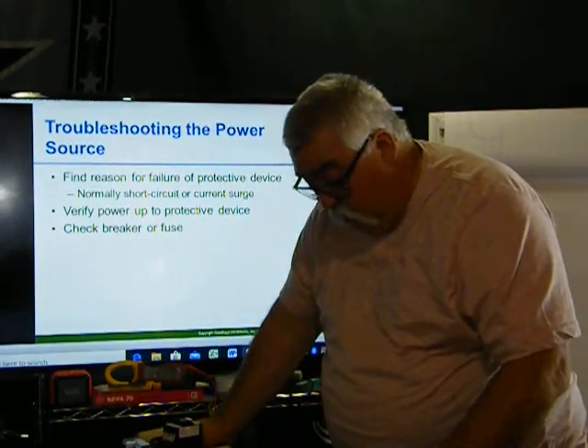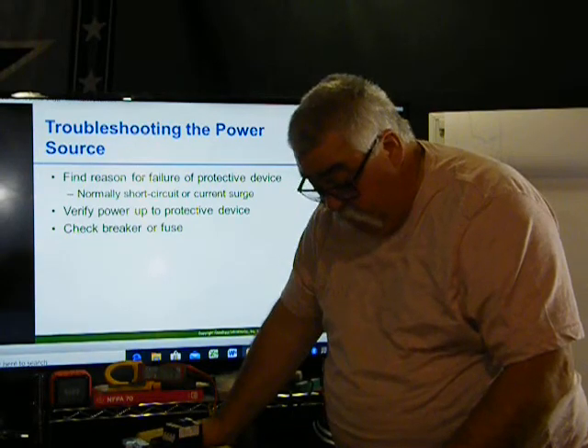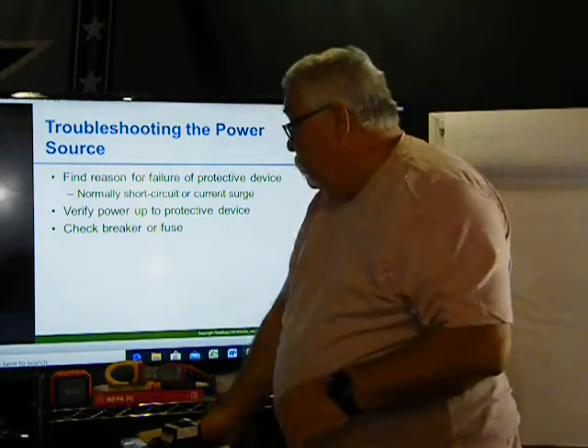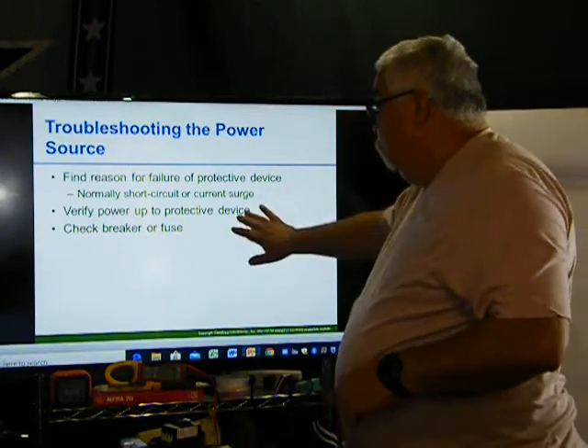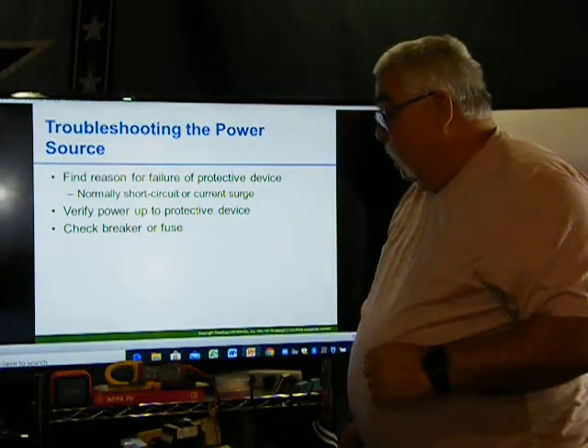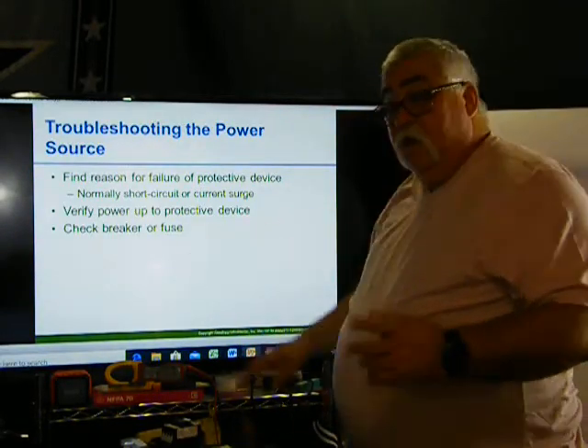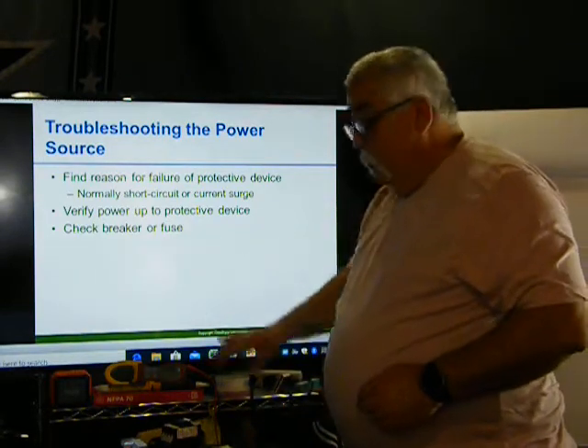If power is present, the breaker or fuse should be checked. Connect one side of the voltmeter. Let me go to the next break. So first we verify that we have power. Once we have power and it's still not working, then we can go back and look.